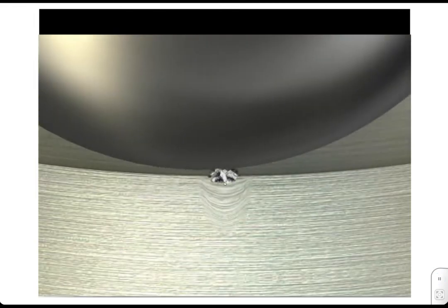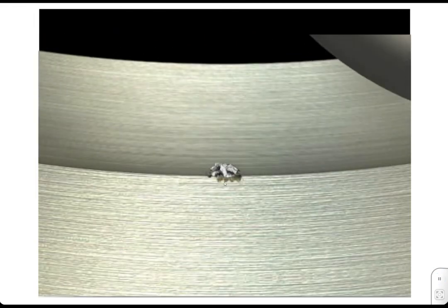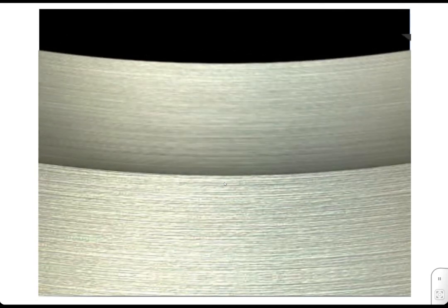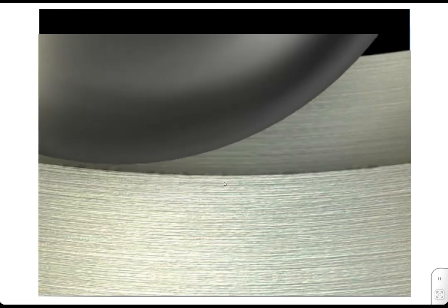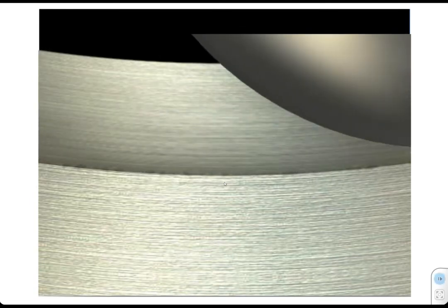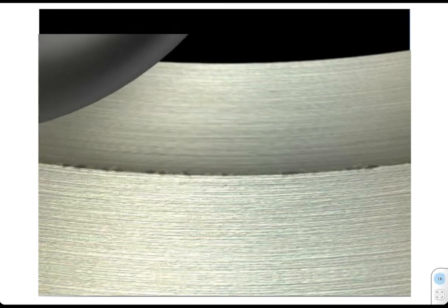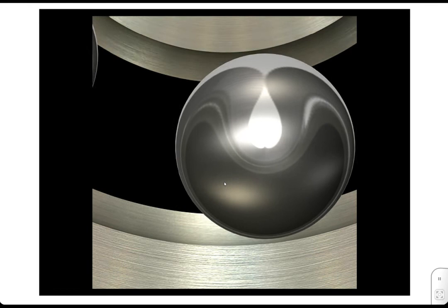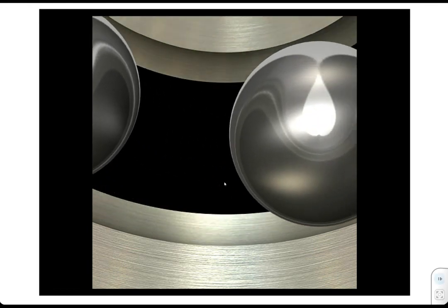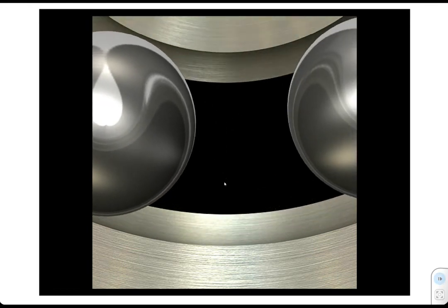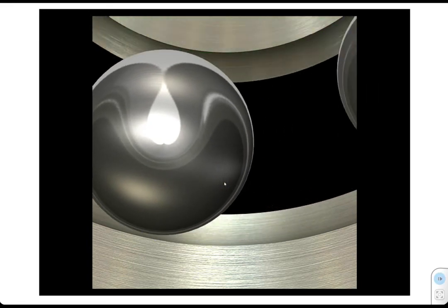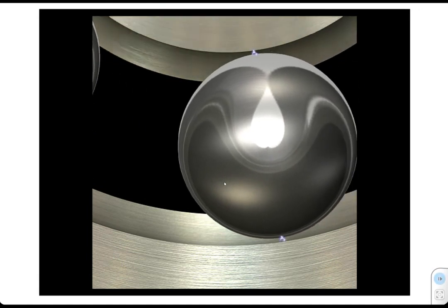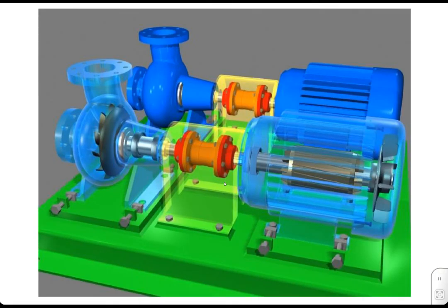I've already shown you what happens when there's contamination. It's very harmful to the machine. Instead of being sort of rolled over, creating indentation, sometimes those little particles can sort of skid along in front of the rolling element, and it sort of scores the surface, it damages the surface, which I hope you can see there. And we can have a situation where there's current passing through the rolling elements. Now this is common with DC drives, but also with variable frequency drives, and that also damages the surface of the bearings and gears for that matter.